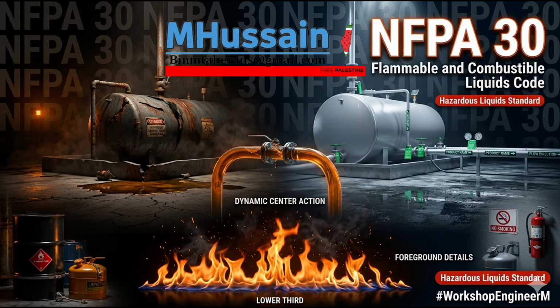Right. If you've driven past a coastal refinery, you've seen these. A fixed roof tank is visually straightforward, a massive cylinder with a conical or domed steel roof permanently welded to the top. And the inherent danger there lies in the empty space inside. As the liquid level goes up and down during transfers, there is always a void space between the liquid surface and the fixed roof. That void space is where the vapors accumulate. Right. It's a constantly shifting environment where the vapor-to-air ratio frequently enters the critical explosive range.